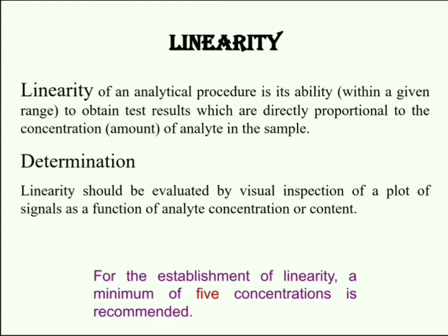Next analytical performance characteristic is linearity. The term linearity refers to the property of scaling. Linearity is a type of mathematical relationship that can be graphically represented as a straight line graph. Linearity of an analytical procedure is its ability to obtain test results which are directly proportional to the concentration of analyte in the sample. Linearity should be evaluated by visual inspection of a plot of signals as a function of analyte concentration or content.